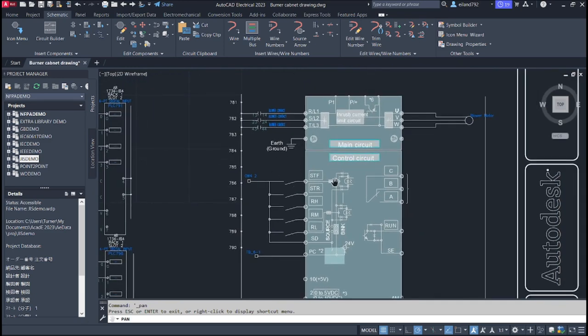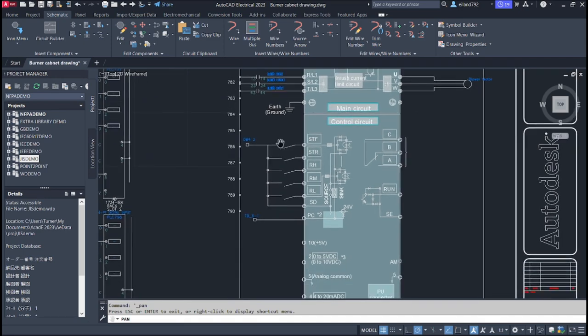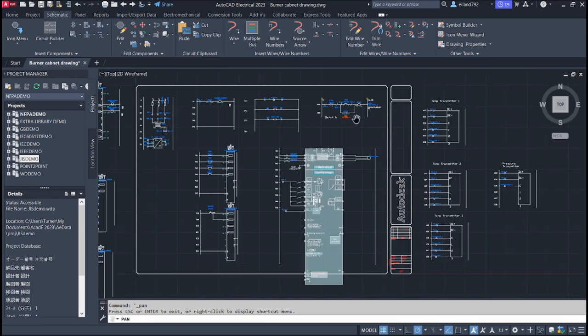Here's our frequency drive. It's powered with 3 phases, and then those 3 phases end up going to the motor. Then I originally was going to do this through Modbus, but didn't have enough time to figure that all out. So I just have an output from my .io that when it's connected, it activates this start forward right here. And then we just have this running a common right here. This is 24 volt control.